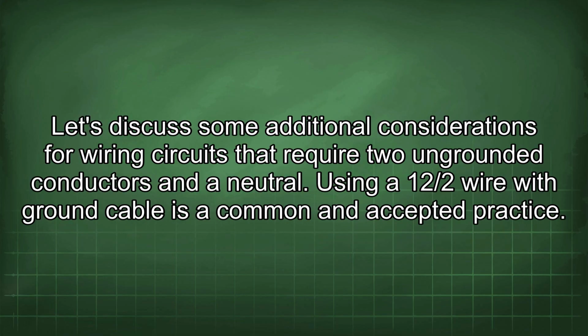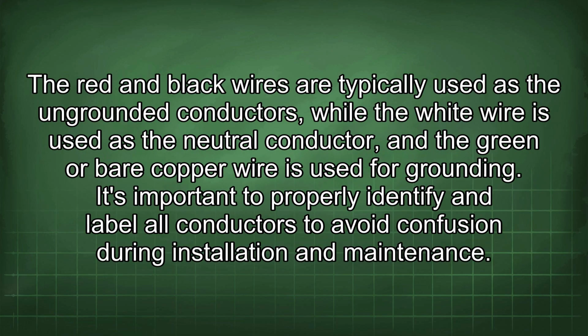Let's discuss some additional considerations for wiring circuits that require two ungrounded conductors and a neutral. Using a 12/2 wire with ground cable is a common and accepted practice. The red and black wires are typically used as the ungrounded conductors, while the white wire is used as the neutral conductor and the green or bare copper wire is used for grounding. It's important to properly identify and label all conductors to avoid confusion during installation and maintenance.